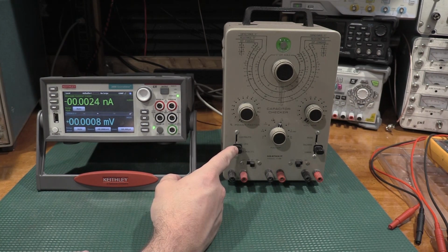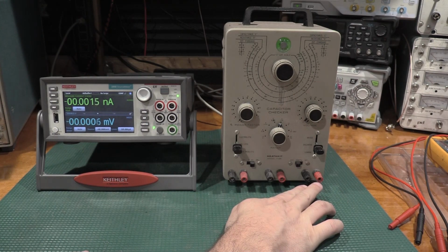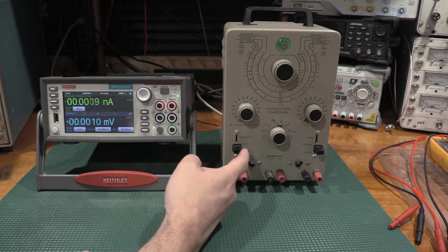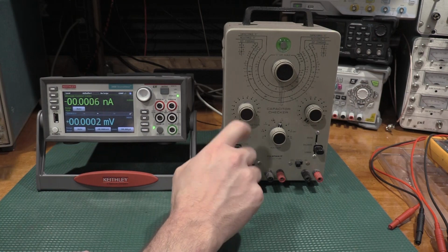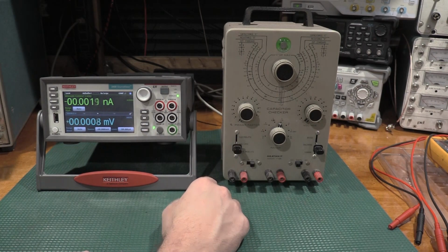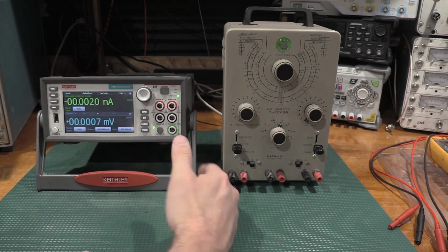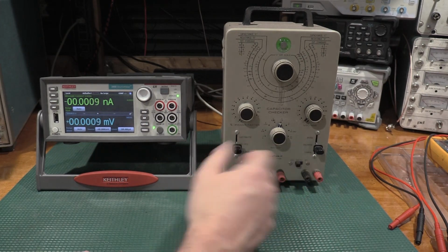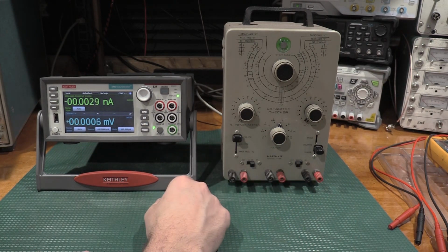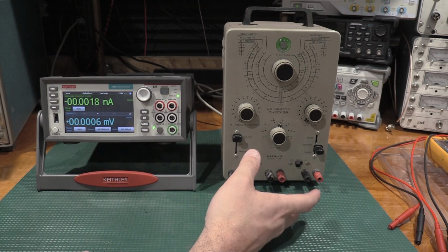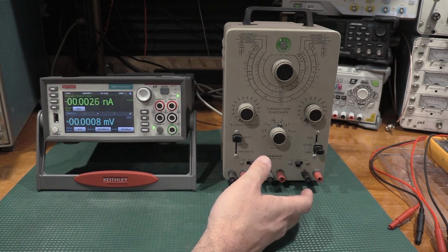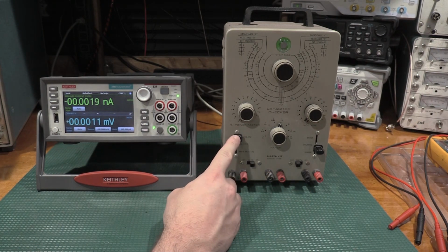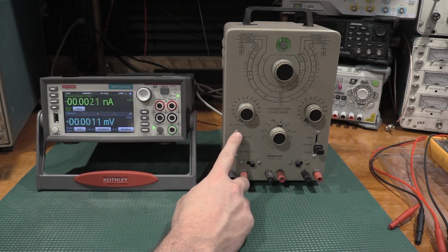So when you calibrate one of these, you have the test voltage here. And all this switch is doing when you move this up and down is adjusting the test current. Not the charge current, that's the same. It's the leakage current. So if you have it in electrolytic, which is the worst one, if I remember the spec sheet, or if I remember the calibration document correctly, it's 25 microamps. So anything under 25 microamps will close the eye, and it'll be a passing, or it'll open the eye and it'll be a passing grade.